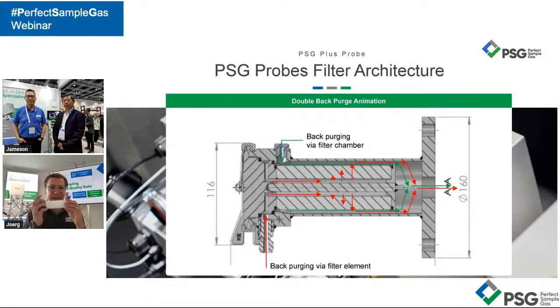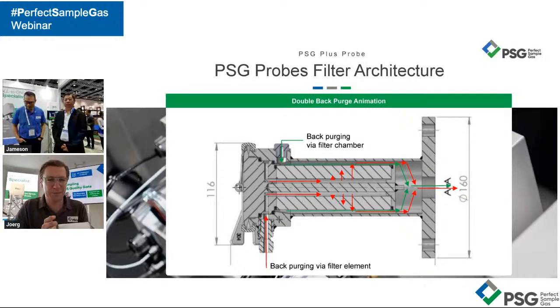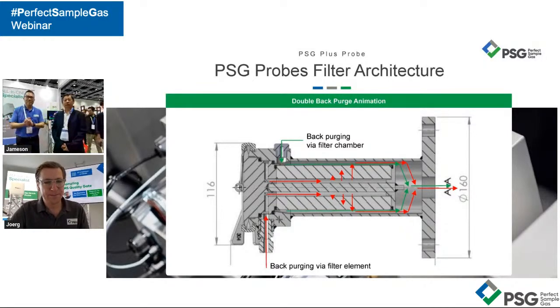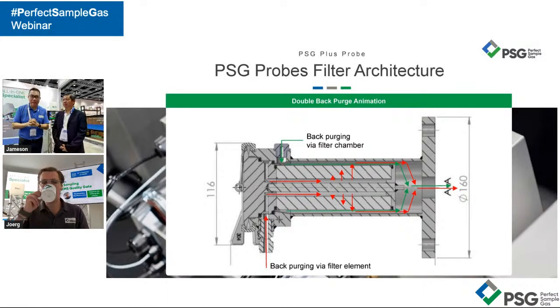Why do you think this architecture and the filter element inside the probe is so important? Yeah. So for stack emission, especially in Asia, every specification asks for back purge, blow back. But many people forget that back purge is only a philosophy. And where lies the secret? It is the filter element. Therefore, it is important that our customers understand the construction, the architecture of our probe, and also the filter element. Without all these things, once the particle enters the ceramic filter, it is impossible to have a back purge.